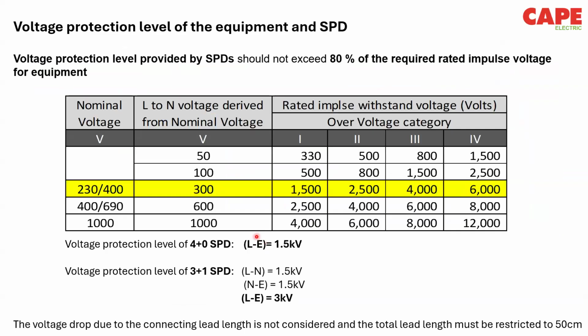So for example, if the voltage protection level of an SPD from line to earth is 1.5 kV, for a 4+0 SPD, it is going to be 1.5 kV. If you take a 3+1 SPD, they will declare two voltage protection level values. One is line to neutral, which is 1.5 kV, and neutral to earth, which is also 1.5 kV. So that makes the total voltage protection level 3 kV, that is from line to earth. Okay. Do remember, line to earth voltage protection level is a mandatory requirement from standards.